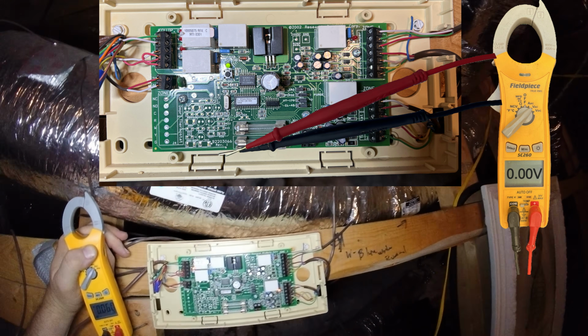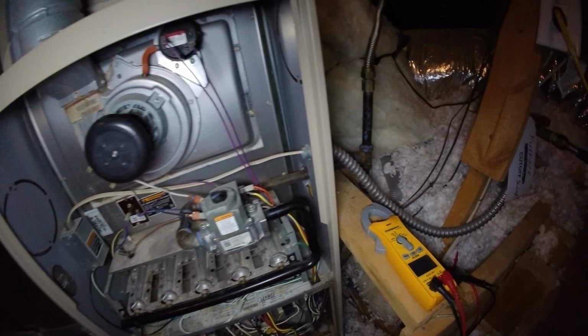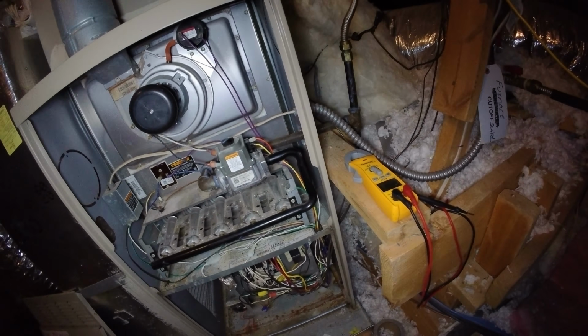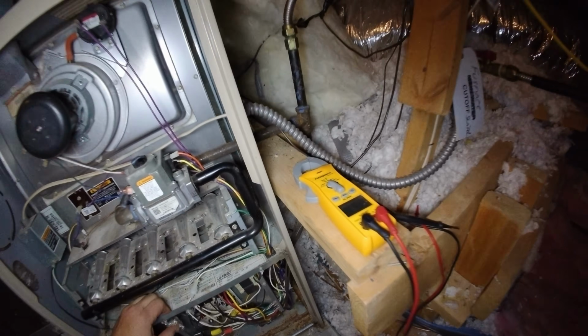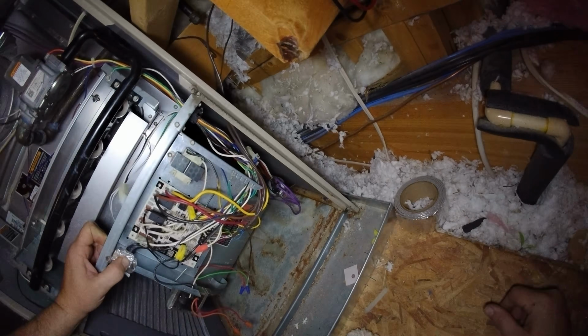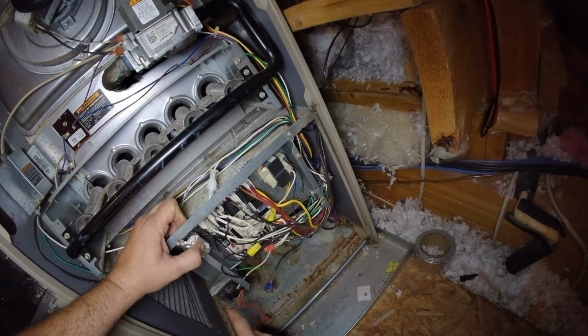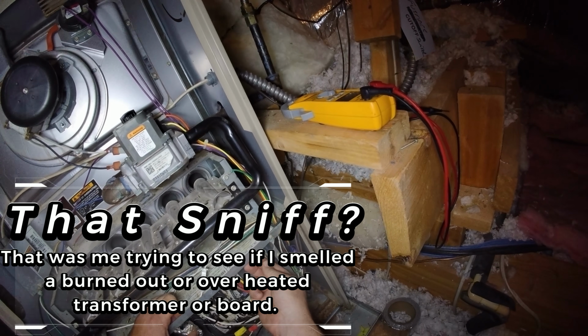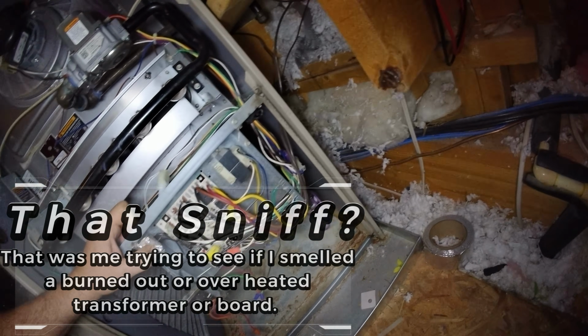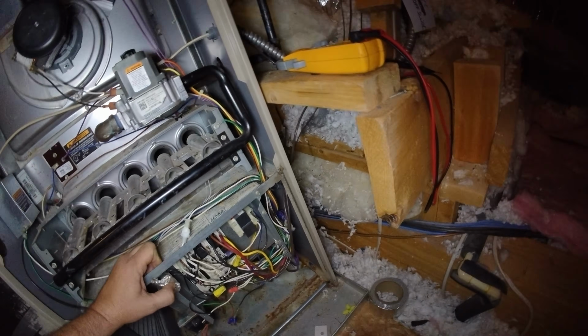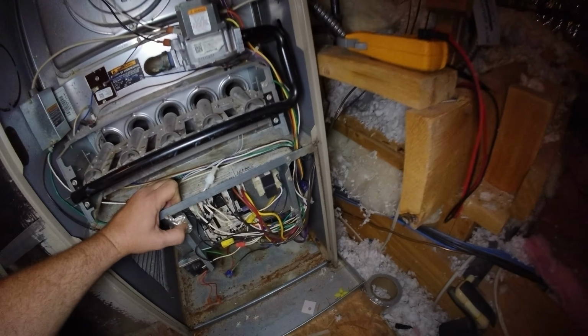I know we have to have 24 volts because it's lit up. There again, this can be operating on a second transformer, so it may not even be attached to this guy. So let's take this apart and get in there. Right away, even pressing that in with my finger, we don't see an LED right here. That transformer is warm, so that one's buzzing.